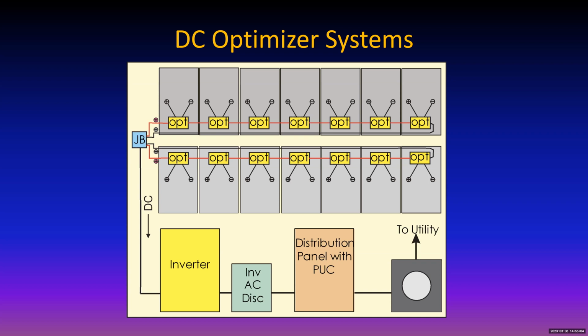So notice the difference here. This is a series connection now on these optimizers, not a parallel connection like we had with the common voltage for the microinverters. Here in the optimizers, we have a common current, but since each of those little yellow boxes contains its very own maximum power point tracking circuitry, if they have different exposures, they will all operate at different voltages, but they have to operate at the same current because they're in series. This is the output current.